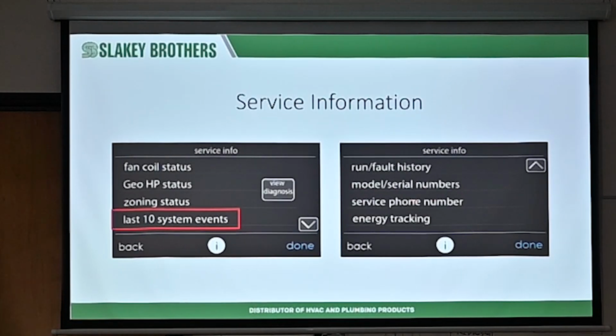This I love, so I don't have to go outside. You select this part, model numbers and serial numbers. I can get my control model number, serial number, furnace model number, serial number, and everything. If you changed out a circuit board though, all that stuff's gone. If you change out the furnace circuit board or the outdoor circuit board, it'll tell you what it is, but it's not going to give you the serial number, because that was embedded when they made the equipment overall. But it's just a neat little feature to have.